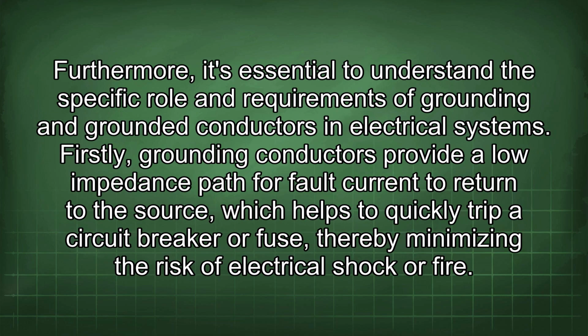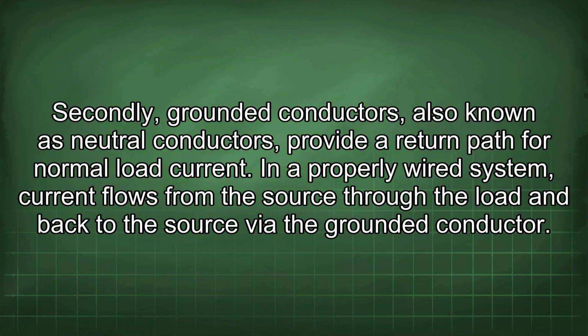Furthermore, it's essential to understand the specific role and requirements of grounding and grounded conductors in electrical systems. Firstly, grounding conductors provide a low impedance path for fault current to return to the source, which helps to quickly trip a circuit breaker or fuse, thereby minimizing the risk of electrical shock or fire. Secondly, grounded conductors, also known as neutral conductors, provide a return path for normal load current.